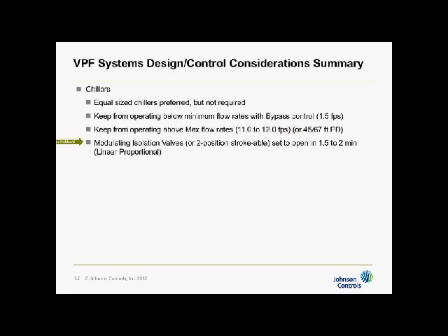Modulating isolation valves are going to be necessary. You'll see why in a few minutes, as opposed to a two-position valve. Two-position strokeable can work if it's linear valve position to flow. Set them to open over 1.5 to 2 minutes, linear proportion, and I'll show you an example of why that's important with a VPF system in a few minutes.